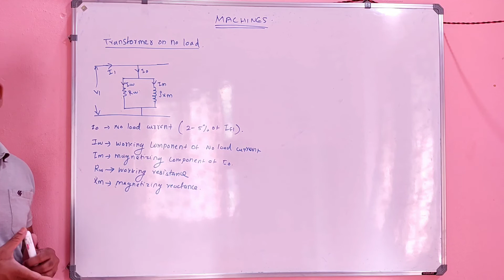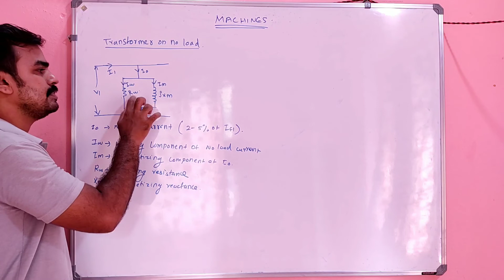Whenever you apply a certain voltage to the transformer on no load, the current drawn by it is called the no load current I0. This no load current is utilized for two things. One, a small portion is used as heat of the core. Even though there is no load, a small heat is generated there. The heat comprises eddy current loss, hysteresis loss and a small amount of copper loss. The loss component of that no load current is called IW, and loss in the form of heat means there should be some resistance. We can represent it as an equivalent resistance, called RW, or working resistance. And XM is the reactance which is responsible for the setup of flux in the core.